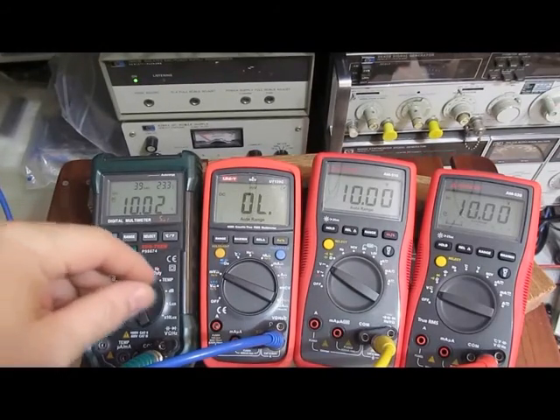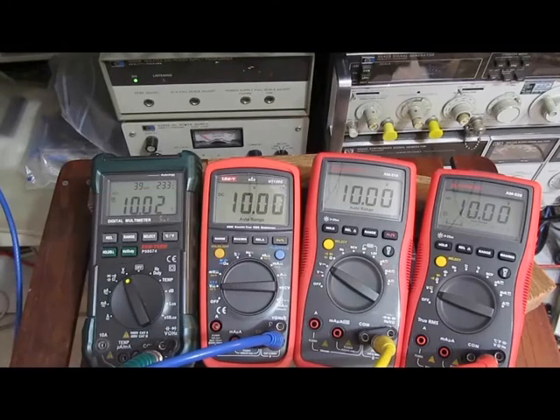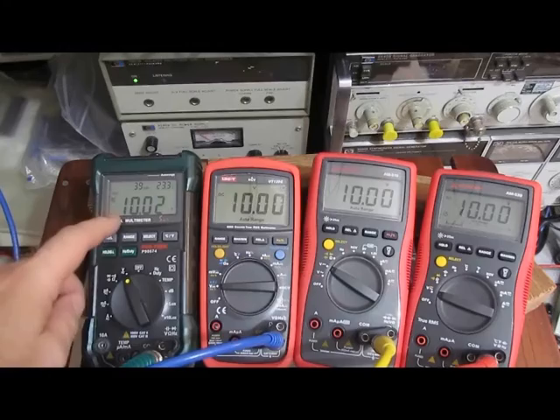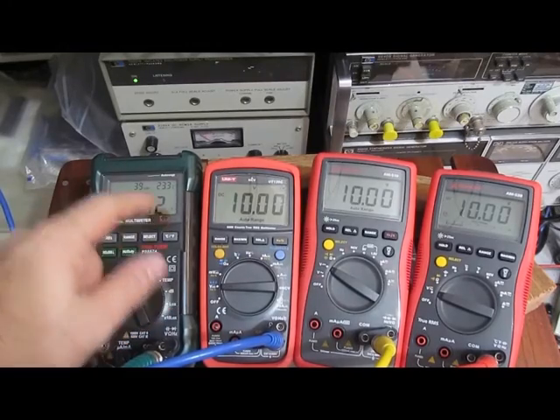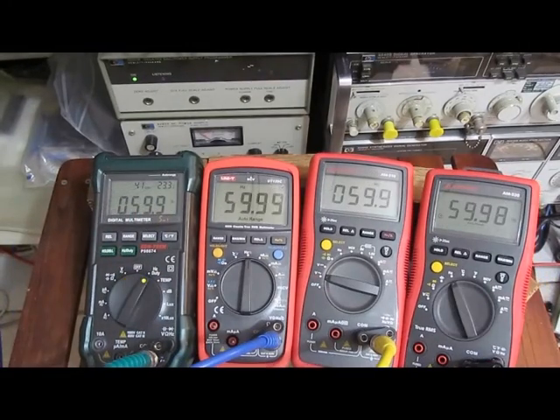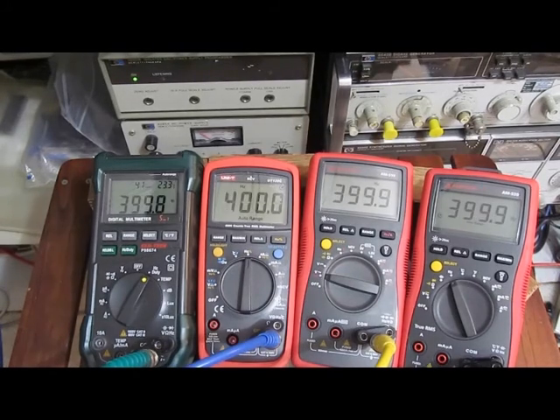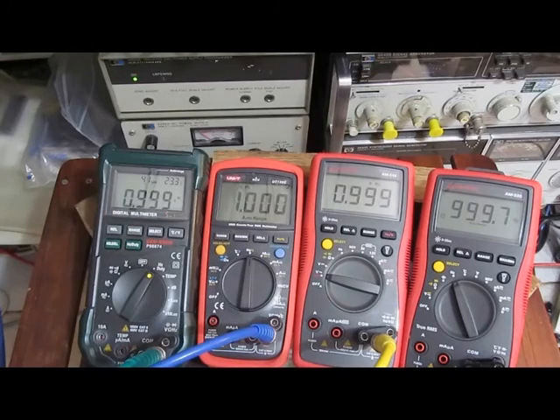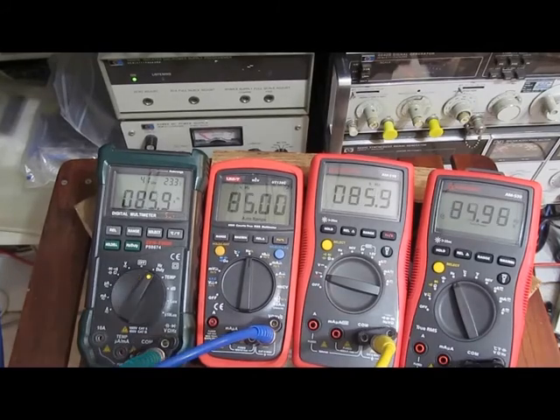This is with 10 volts applied. So all meters basically fairly close. The Mastech's a little hot, about 20 millivolts high in this range. This is looking at the line frequency, again all roughly 60 hertz. This is 400 hertz, 1 kilohertz, 10 kilohertz, 40 kilohertz.